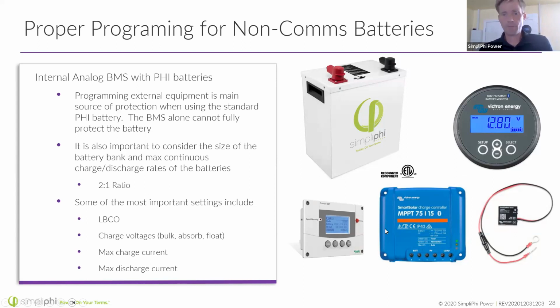What we're showing in the bottom left is the Schneider SCP, which allows similar functions. And some of the most important things to include when you're programming your charge controllers to work with PHI batteries, non-communicating batteries, are to properly put in the LBCO. The very lowest we recommend that you set your LBCO would be 48 volts, and that's for 100% depth of discharge. So LBCO is low battery cutout. You don't want to discharge your battery beyond that. In fact, once you get down to 48 volts, there's almost zero energy left in the batteries, right?